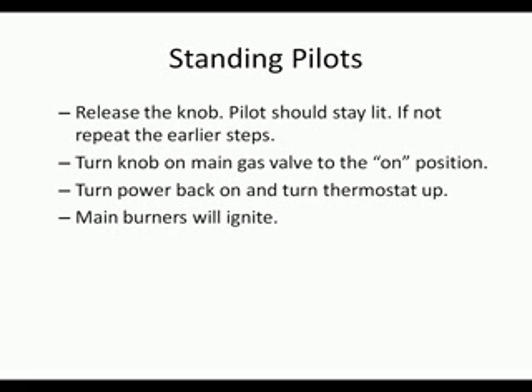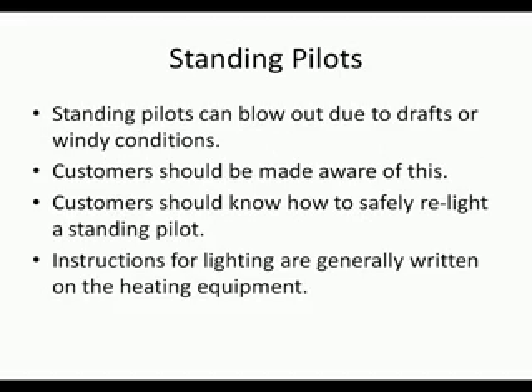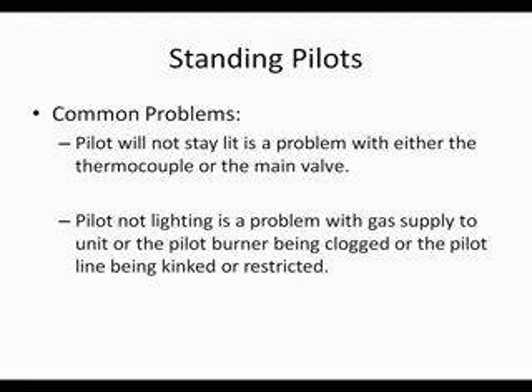To light the standing pilot, as I said earlier, turn off the heating unit, turn the knob on the main gas valve to the pilot position, push down and hold the knob. Light the gas at the pilot with a match, lighter, sparker, or anything like that. Once the pilot is lit, keep holding down on the knob for at least 1 minute. Release the knob, the pilot should stay lit. If not, repeat the earlier steps. Turn the knob on the main gas valve to the on position. Turn power back on and turn the thermostat up. The main burners will ignite.